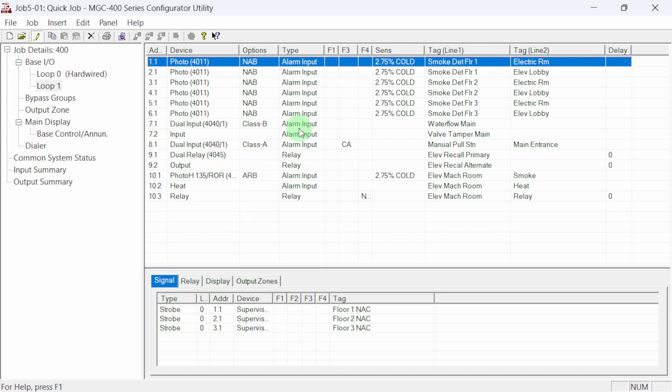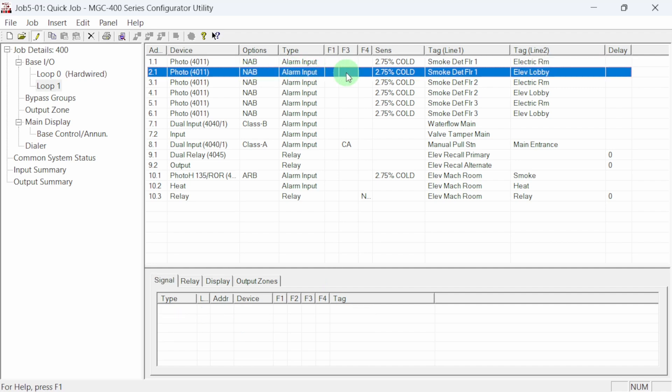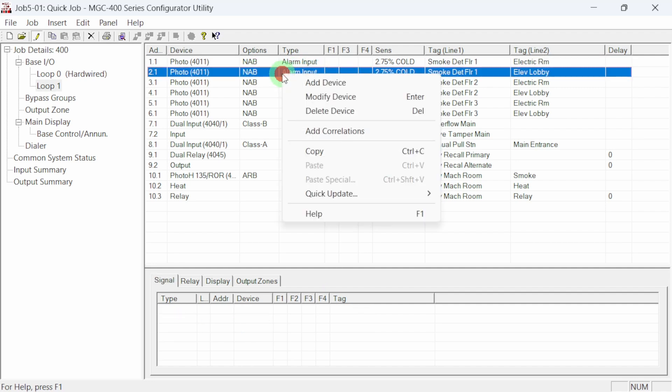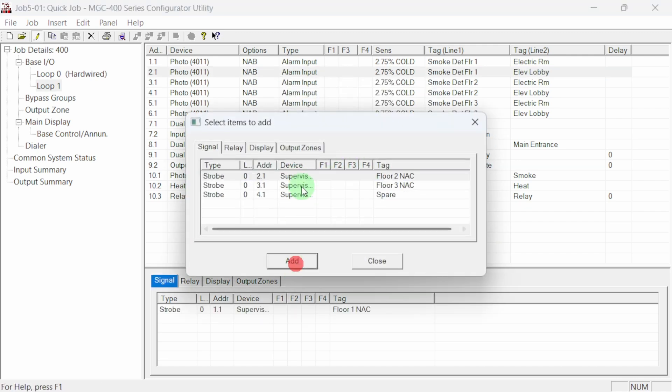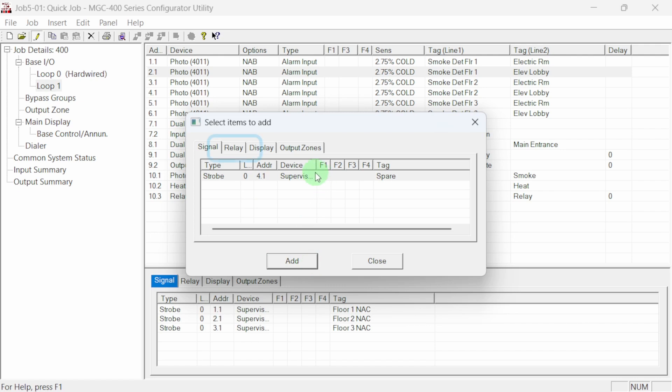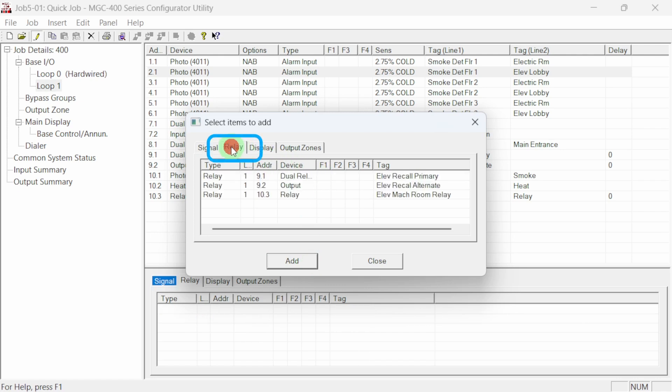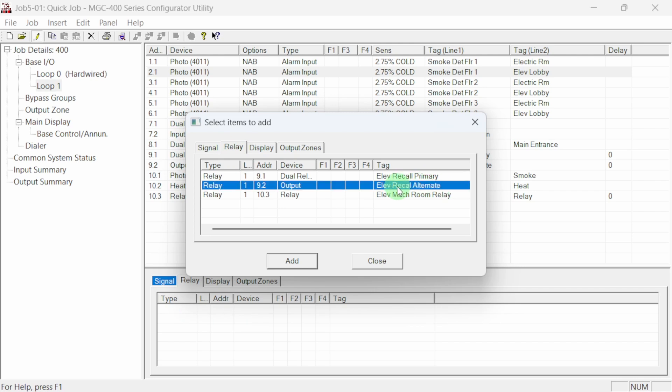Let's correlate our first floor elevator lobby smoke detector to trigger the NAC circuits and the alternate floor recall relay. Right click on the device and select add correlations. Add the NAC circuits. In addition to the NACs, we want to add the alternate floor relay. Select the relay tab and choose the relay in the selection list, highlight it and click add.